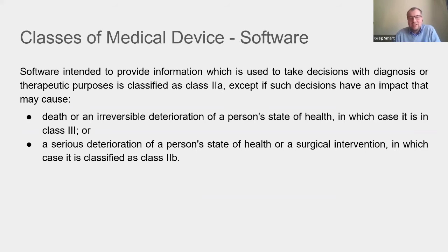Now, it's actually quite hard to think of an example of software which might be considered a medical device according to the definition and the rules we looked at a few minutes ago, but which doesn't have some diagnostic or therapeutic purpose. So it seems that by introducing these new regulations, the MDR has effectively made Class 1 a closed door as far as software developers are concerned. It's unlikely, if you are involved in medical device software, that in future you will be a Class 1 device. And if you're listening to this and you think, I can think of an example, then please do let me know.